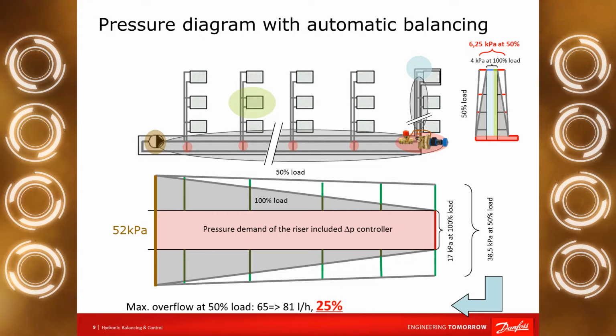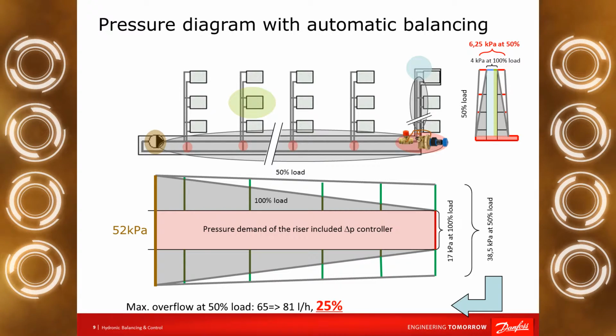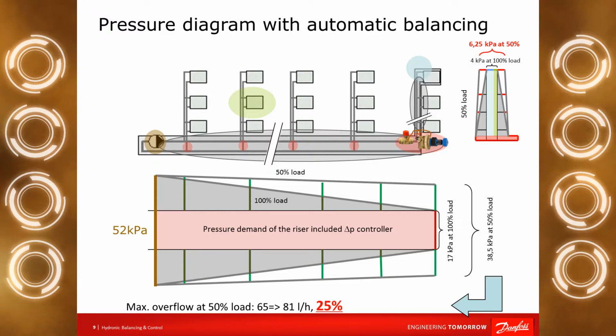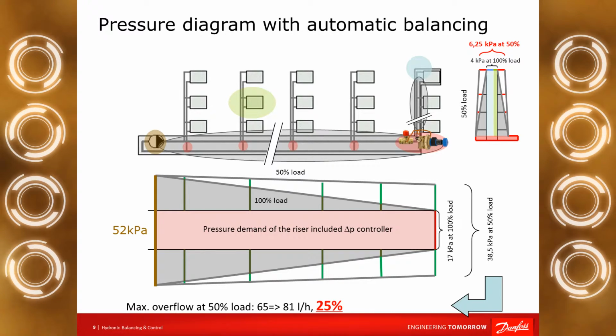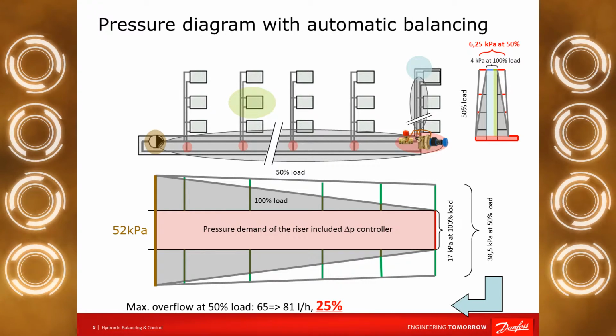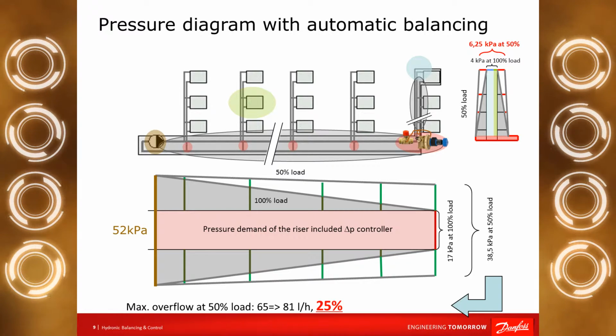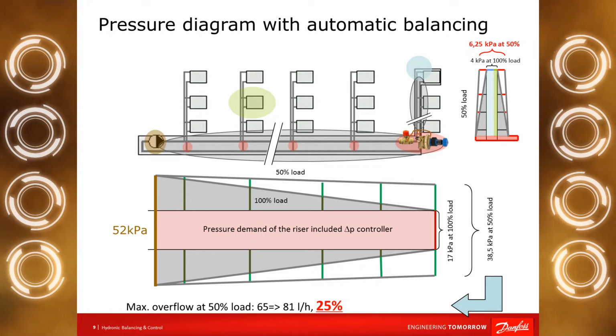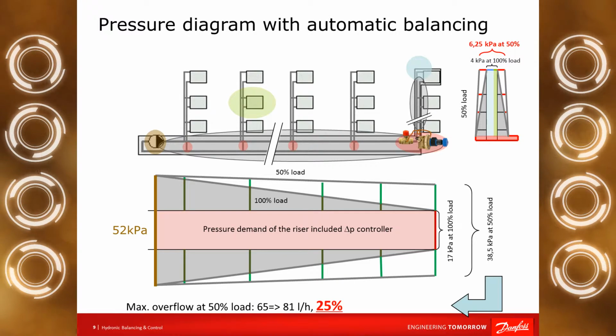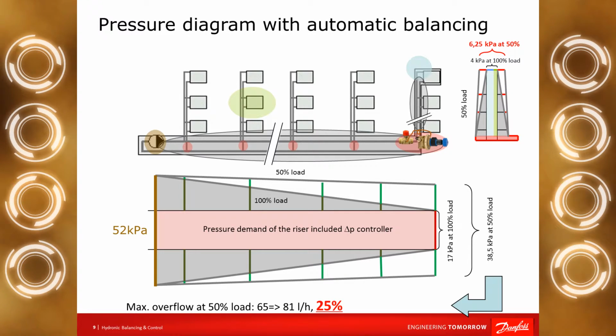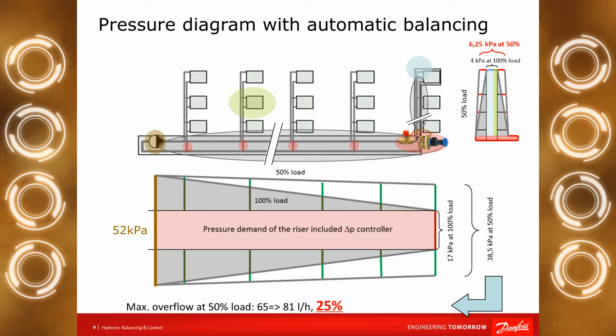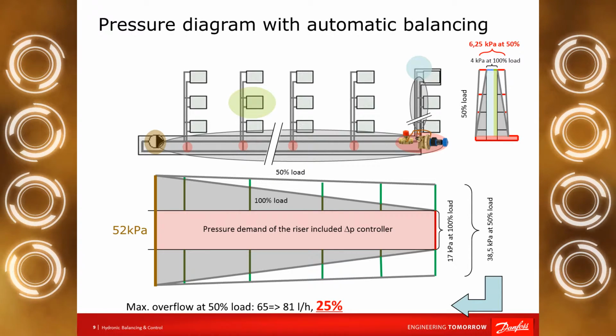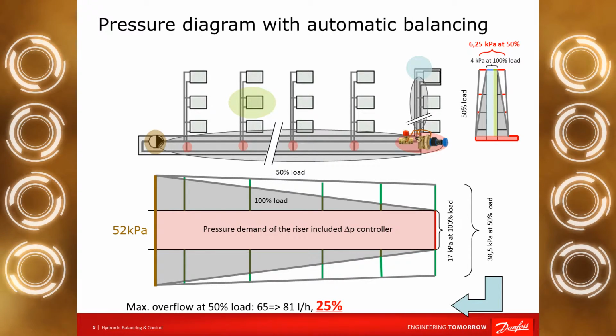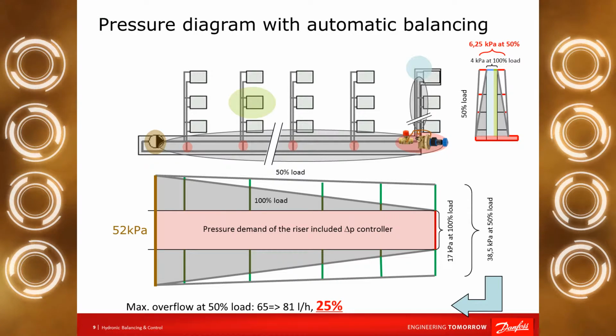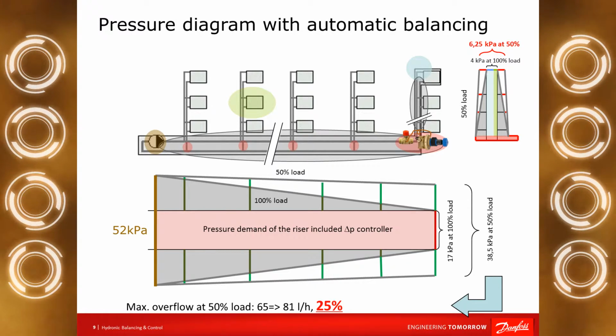What is the overflow here? Now we can see the originally 4 kilopascal overpressure increased up to 6.25 only. It's not so big. Of course, the pressure is bigger than we expected, so there will be some overflow. But this overflow is only 25% compared to the previous system when we had 3 times more flow rate. So this is the situation at the far end point of the system.